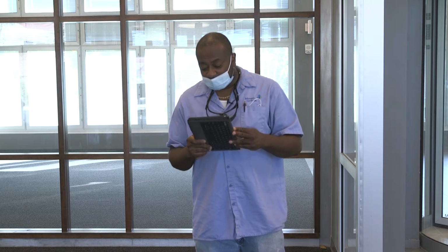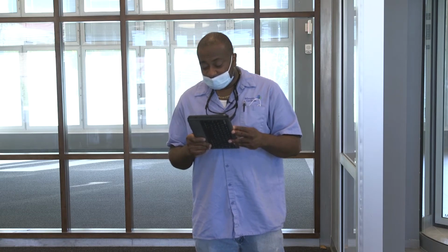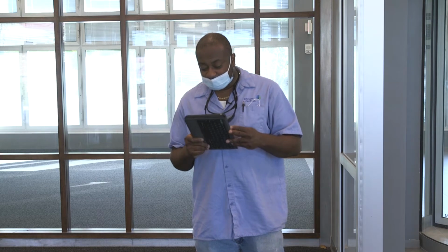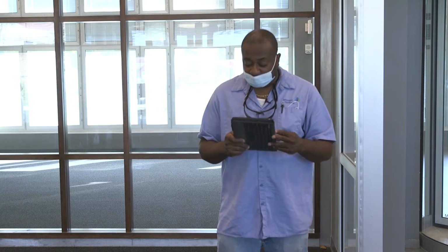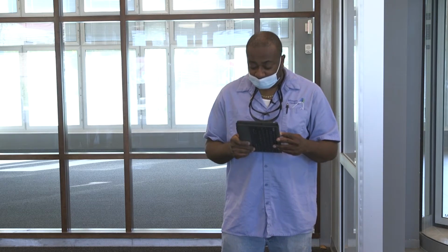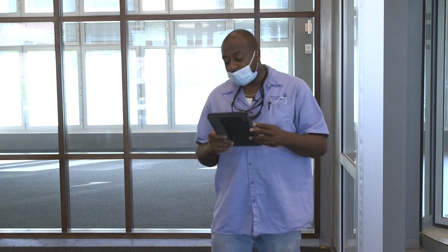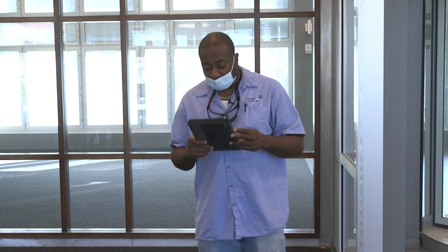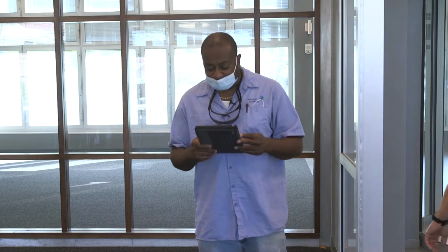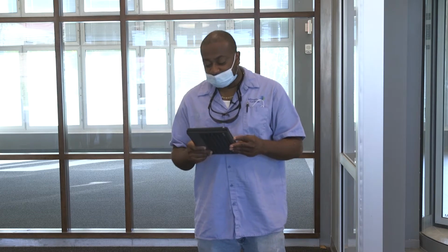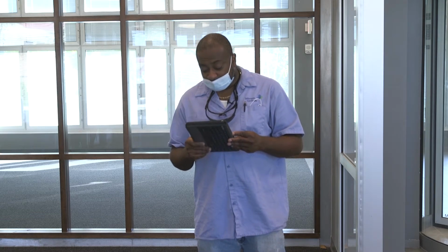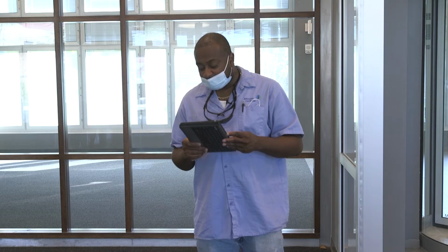When the thermostat calls for the second stage of cooling, a 24-volt signal is provided to the S2 terminal directly from the condenser or heat pump. This signal closes the coil of the solenoid control relay. The relays RY1 and RY2 operate in series, then energize the solenoid valve, allowing refrigerant to flow through the upper refrigeration system. Note, the unit controls are designed to allow lead lag compressor operation.